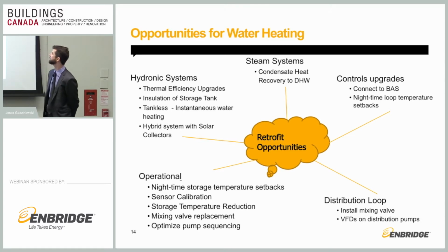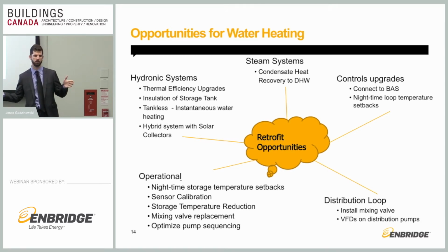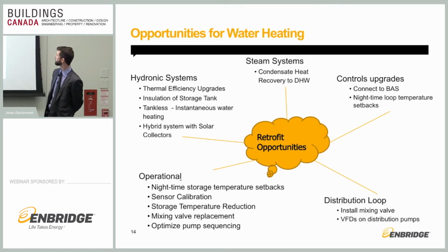Controls upgrades, same thing, connecting to the BAS, doing some setbacks if you can. Maybe in the daytime, if you've got a large tank and you know your demand's high in the day, you need to have that water at 150 to maintain the load for the day. But at night, you're not going to need a tank full of 150 degree water. You could probably drop that down maybe 5 or 10 degrees Fahrenheit just to meet the overnight load, and it would be appropriate. So a little bit of savings there.